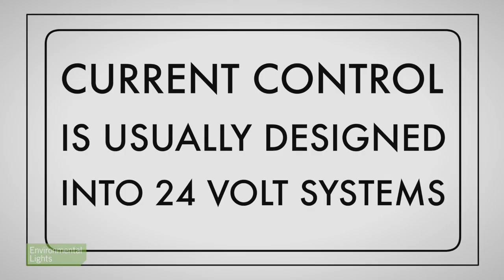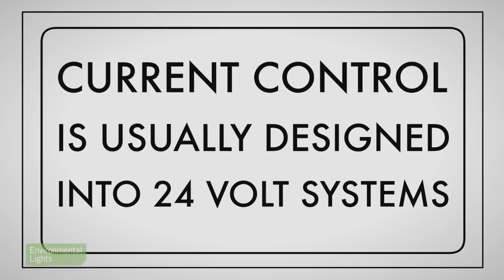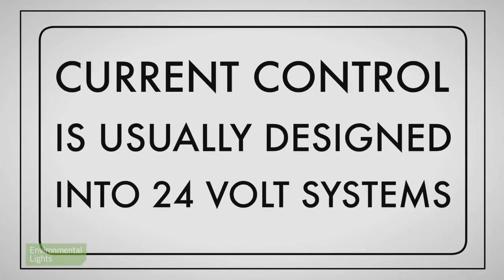Three things to remember. Number one: current control is usually designed into 24 volt, not 12 volt systems, because the limit of Class 2 wiring at 24 volts is 100 watts whereas it is only 60 watts at 12 volts. So you can more easily create larger layouts at 24 volts than 12 volts, and those larger layouts are exactly where the current control approach helps the most.